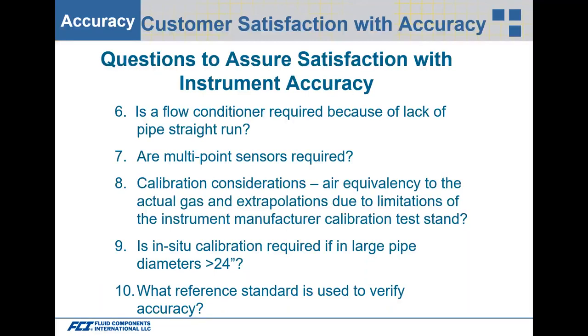Is in-situ calibration required for large pipe diameters, say 24 inches or larger? You can use a single point and perform in-situ field calibration: install the flow meter, insert an S-style pitot tube, perform a cross-sectional traverse across the pipe to find the average flow, reinsert the flow meter, compare it to the pitot tube measurements, and make a correction factor to match the traverse result.